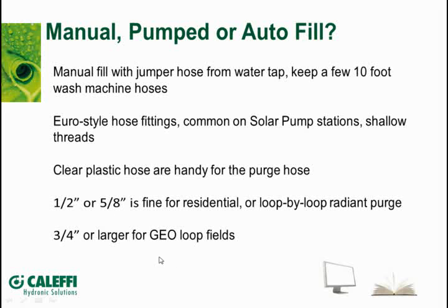Now, if you start doing the larger systems, you start getting into some of the bigger loop fields or even bigger radiant jobs, you're going to have to start looking for some larger diameter. Not only do the tubes that you're going to put the fluid into the system need to get larger, but certainly your connections, instead of just a little 1/2-inch boiler drain or a 1/2-inch ball valve, you're going to now have to provide some bigger connections to be able to put a bigger size hose in there so you can get enough flow through there to be able to push all the air and the dirt and debris out of the system.